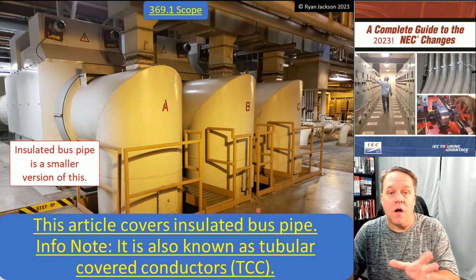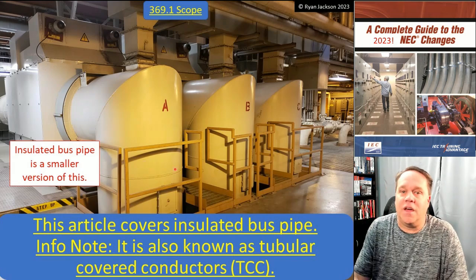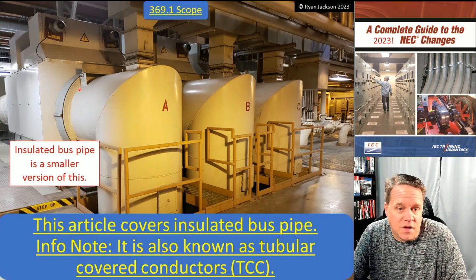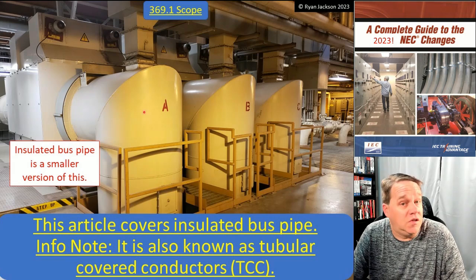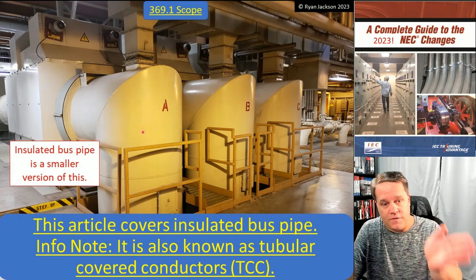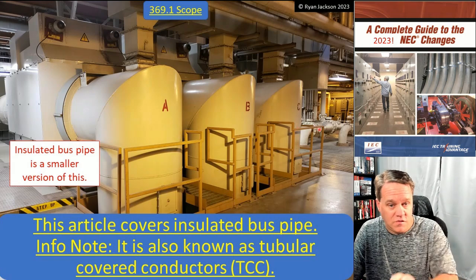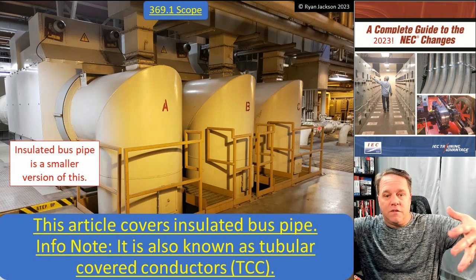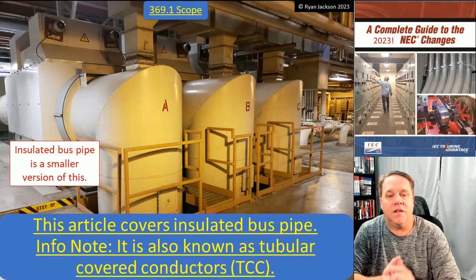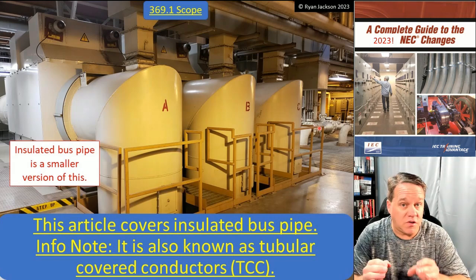You're not going to run into something this big in an NEC regulated application. This is 26,000 volts, 22,000 amps, and yes, that is phase A, phase B, and phase C. So you've got this massive pipe, a duct, and inside of it you've got basically bus bars.